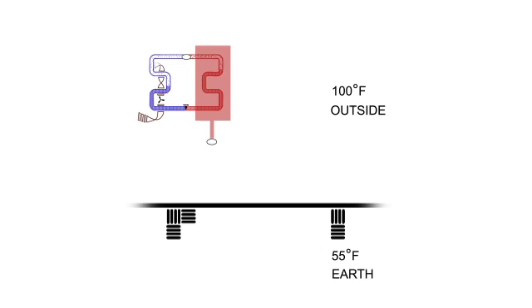In the summertime condition, the compressor reverses direction, and the inside coil cools the recirculated air. Now we are in the opposite predicament, with the same energy-intensive result. The outside coil doesn't want to condense in 100-degree heat. It wants to evaporate. It's hot.